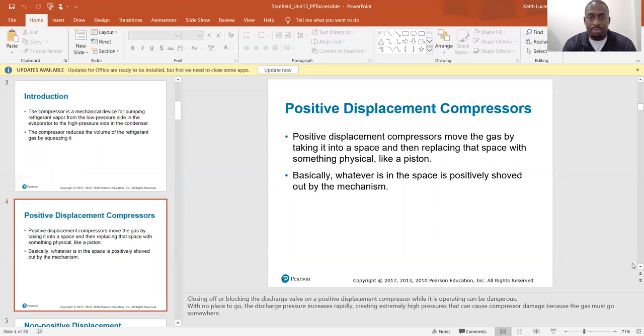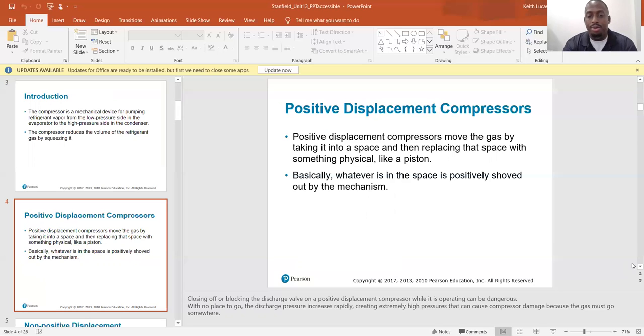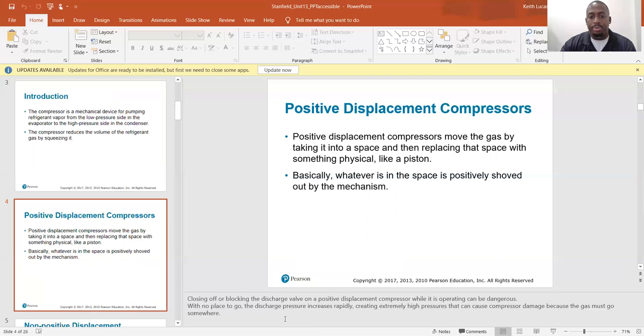Positive displacement compressors move the gas by taking it into a space and then replacing that space with something physical, like a piston. The piston enters the cylinder, takes up the space the refrigerant occupied, and puts pressure on it — whatever is in the space is positively shoved out. Closing or blocking the discharge valve on a positive displacement compressor while it is operating is dangerous; with no place to go, discharge pressure increases rapidly, creating extremely high pressures that can cause compressor damage.